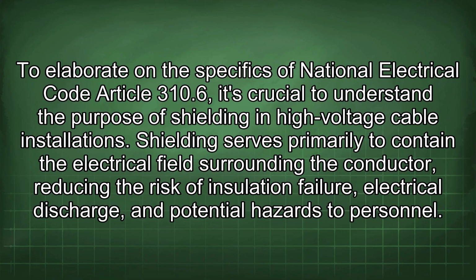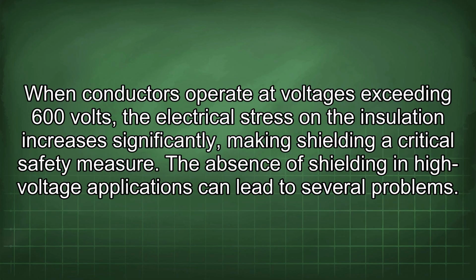To elaborate on the specifics of National Electrical Code Article 310.6, it's crucial to understand the purpose of shielding in high-voltage cable installations. Shielding serves primarily to contain the electrical field surrounding the conductor, reducing the risk of insulation failure, electrical discharge, and potential hazards to personnel. When conductors operate at voltages exceeding 600 volts, the electrical stress on the insulation increases significantly, making shielding a critical safety measure. The absence of shielding in high-voltage applications can lead to several problems.